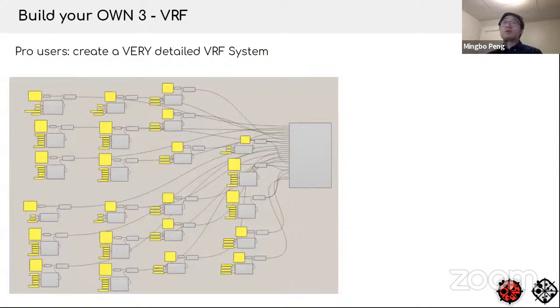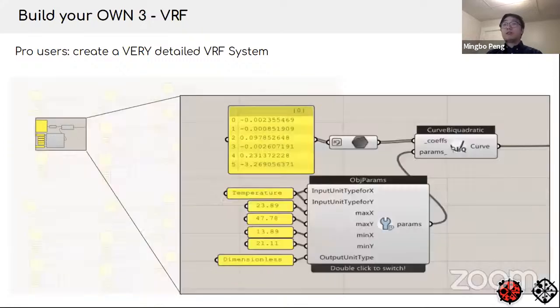One of the most difficult things to model in an HVAC system is the VRF system, because you basically have to model more than 20 performance curves. If you use the default VRF system from OpenStudio, that's very inaccurate because there's no performance curve inside. If you want to model an accurate system, you have to ask a manufacturer or your MEP to provide all those performance curves. Here you have full control and full access to those input parameters.